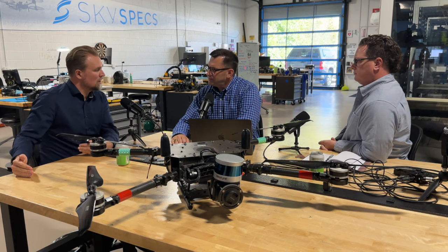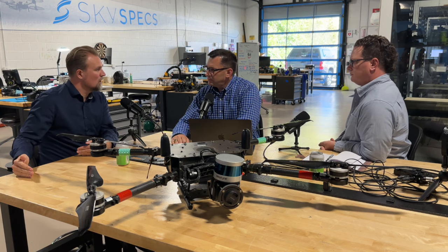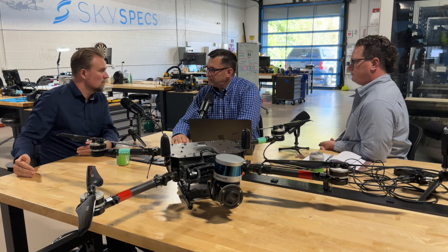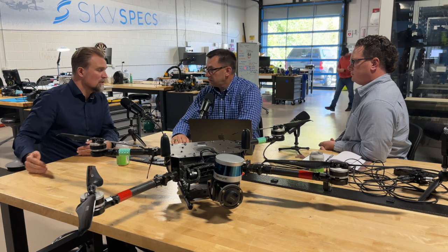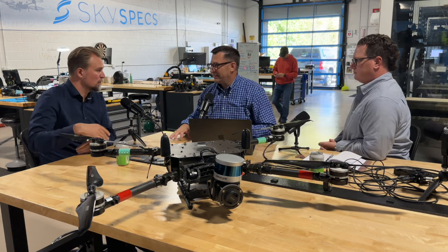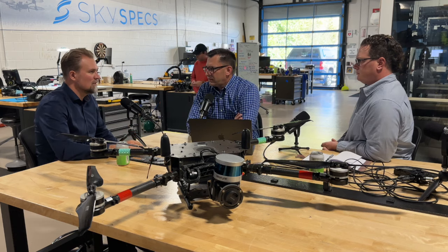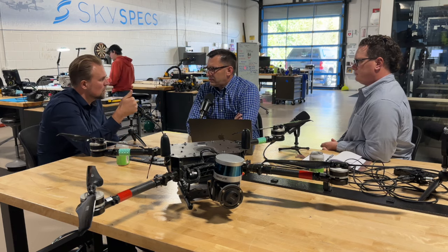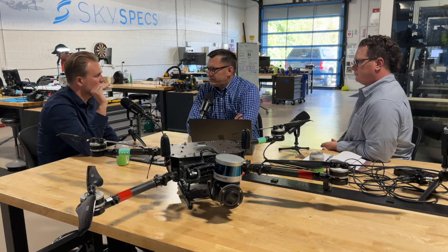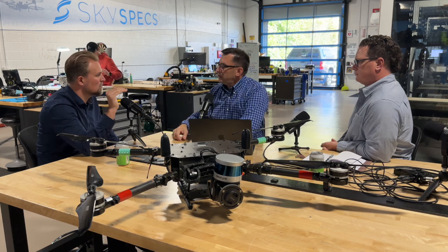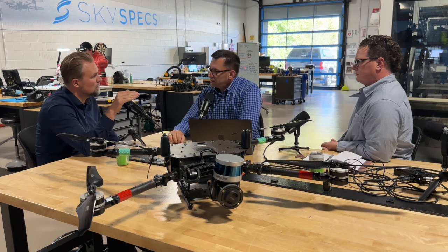So the mechanical variance is huge, and then there are loads of factors that we don't know and can't measure that drive failure mode degradation. It's really hard to measure loads, for example, on a live turbine. You can approximate it with power curves, but you can't really do it. Right. And how is the individual turbine lubricated, and cooling systems, how are they running? It's a very, very complex problem, and they all affect the remaining useful life.